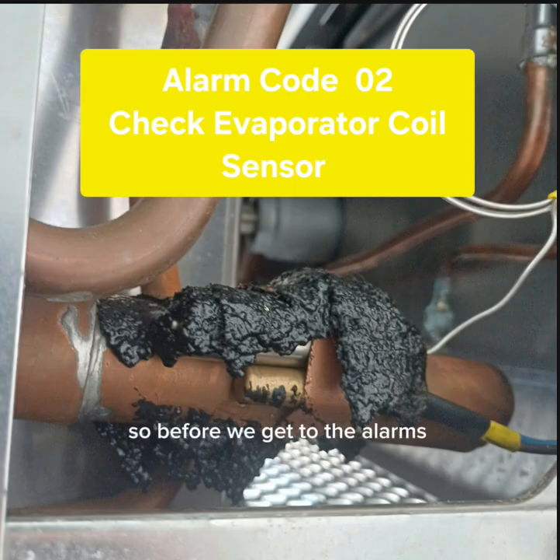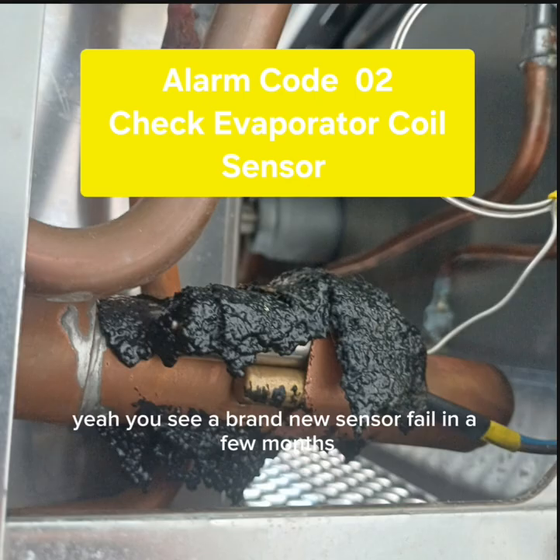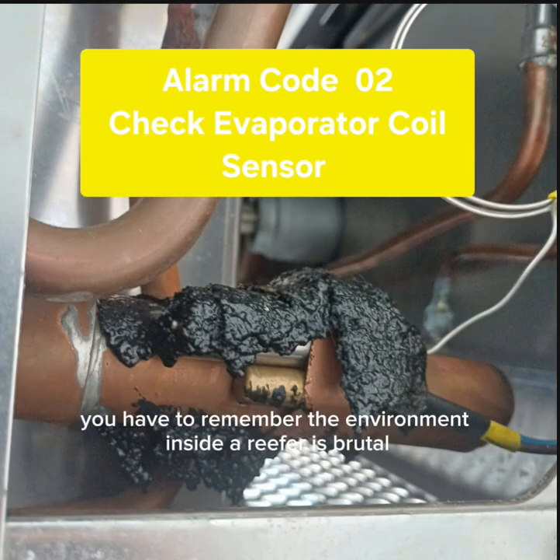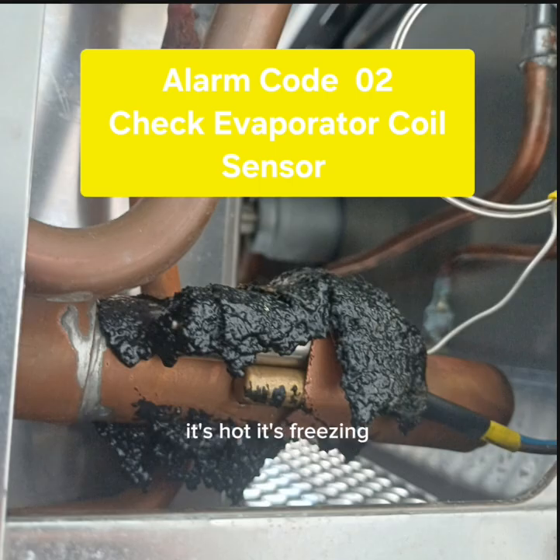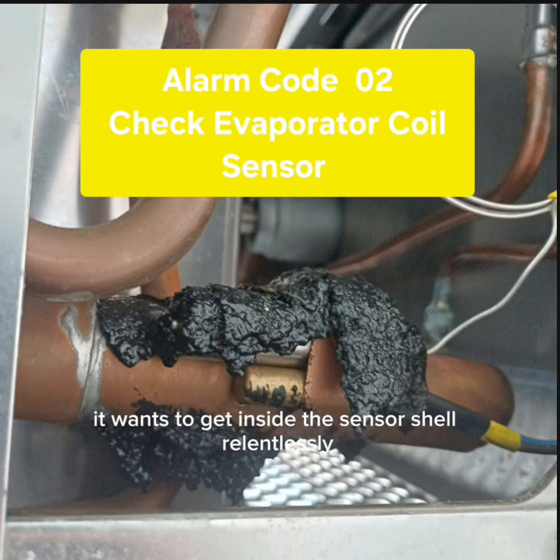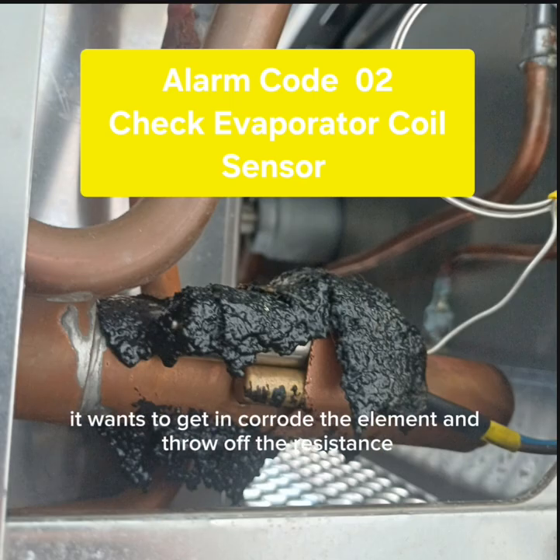So before we get to the alarms, let's talk about installation. You mentioned a lot of failures are, well, self-inflicted. That sounds frustrating. Oh, it is. It's heartbreaking. You see a brand new sensor fail in a few months because of how it was put in. You have to remember, the environment inside a reefer is brutal. It's hot, it's freezing, it's wet. Moisture is the number one enemy. It wants to get inside the sensor shell. Relentlessly. It wants to get in, corrode the element, and throw off the resistance.